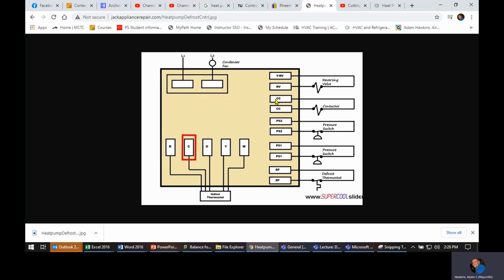So the contactor will have a feed, a yellow in, saying, hey, we need this thing to run. And then assuming everything's in position, so let's say low pressure switch, high pressure switch, for example. If either one of those were bad, we're out. So maybe we're low on refrigerant. We've got a leak and it has tripped on a pressure switch, or maybe the pressure switch is bad, whatever.